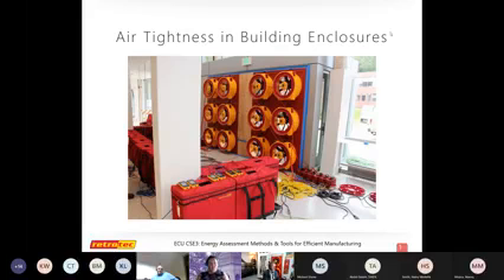And then these things here that you see on the red cases are manometers. And so if we know pressure at the fan and we know the building pressure, we can calculate the flow through the leaks of that building at that given pressure. I'll get into this a little bit later, but I just wanted to introduce what this is.